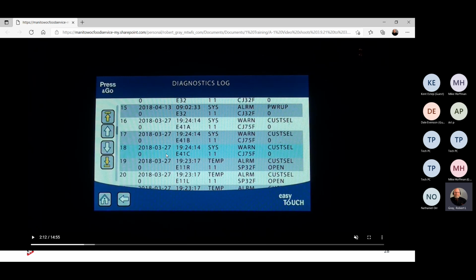Could it be a bad contactor? Sure can. But again, you just turn around and troubleshoot what was going on. Now your solid state relay board is what controls the heat to each heating zone of that lane. So if my solid state relay board has one of the triacs stuck closed, it's going to send power to that heating zone continuously, and eventually it's going to hit 500 degrees and open up the safety thermostat to drop out all 3 phase powers. So again, that's what we're looking at.